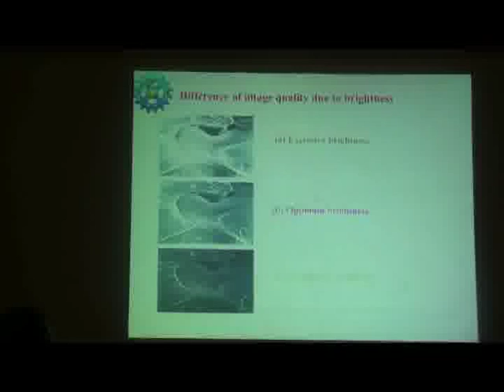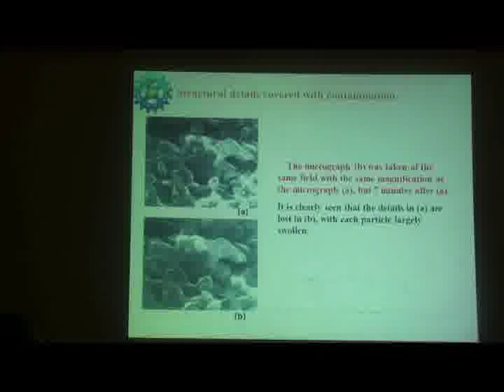When you use the microscope, you should not expose the sample for a long time. When you expose it, the electron beam is going to contaminate it by charging up, or can cause some leaking in the material, and you lose the information. So the exposure should be taken, and the material visualized immediately.